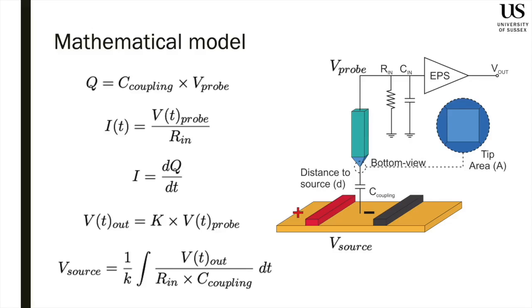The coupling capacitance here refers to the capacitance between the source and the probe, and is governed by its dimensions and its separation to the source. Rin represents the input resistance of the EPS sensor, and Cin represents the capacitance of the sensing probe itself and the EPS sensor. The K factor is a calibration factor and is a combination of the gain used for the EPS sensor and the Cin, which can be varied based on the probe used. By simply integrating the output of the sensor with respect to time, we are able to calculate the voltage of the source under test.